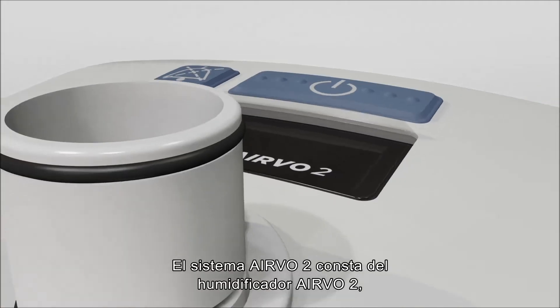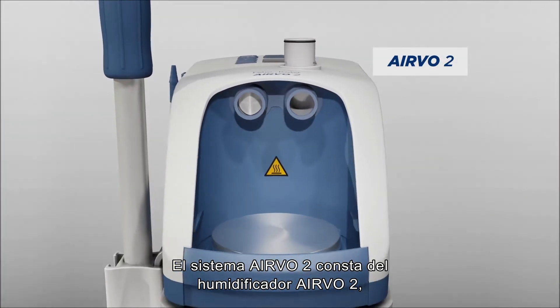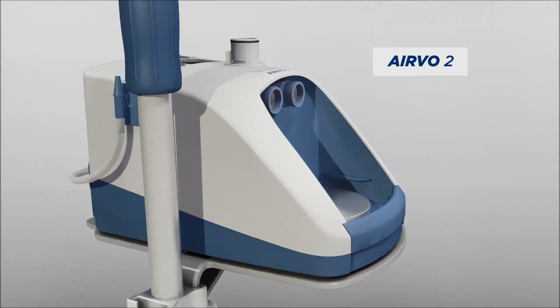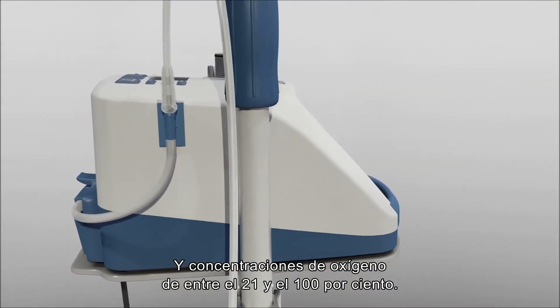The AIRVO 2 system consists of the AIRVO 2 humidifier, which can deliver humidified respiratory gases at flows from 2 to 60 litres per minute, and oxygen concentrations from 21 to 100 per cent.